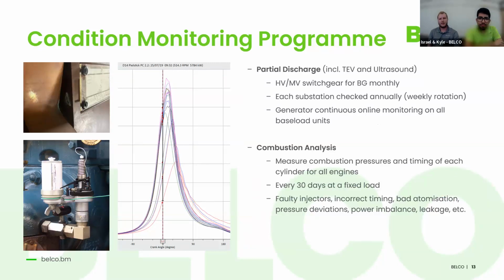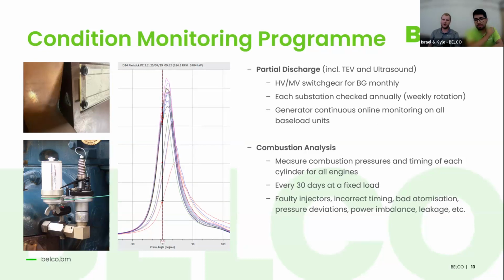Another thing that we check for around the plant is partial discharge, as well as in the distribution network. The HV and MV switchgear around the plant, we check monthly, and then around the island, we check each substation on a weekly rotation. It usually takes us about a year to get through all of them, so we check them annually. As well as that, our reciprocating generators have continuous online monitoring for partial discharge.